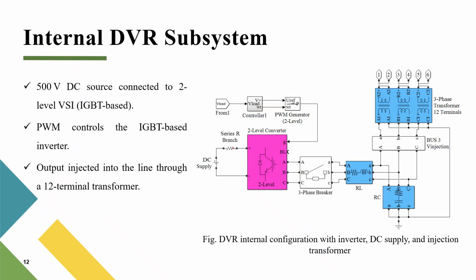Internal DVR subsystem. This figure presents the internal structure of the DVR. A 500-volt DC source supplies power to a two-level voltage source inverter, VSI, composed of 6 IGBT switches. These switches are operated by gate pulses from a PWM generator to synthesize the desired AC voltage. The inverter output is filtered using an LC filter to eliminate high-frequency switching noise. The filtered voltage is then fed into a 12-terminal injection transformer. This transformer allows the series injection of the compensating voltage into the distribution line to correct voltage sag during fault conditions.